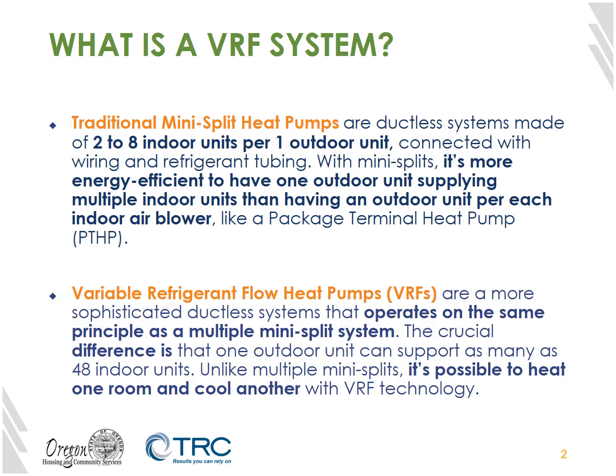So what is a variable refrigerant flow, or VRF, system? We're often asked the difference between a true VRF system and a mini-split system, or what is often referred to as a multi-split system, when you have several mini-splits working together. It is true that the mini-split or multi-split system does use variable refrigerant flow, but the major difference is that each outdoor unit can only control 2 to 8 indoor units with a multi-split system. It is part of the core design of these systems.